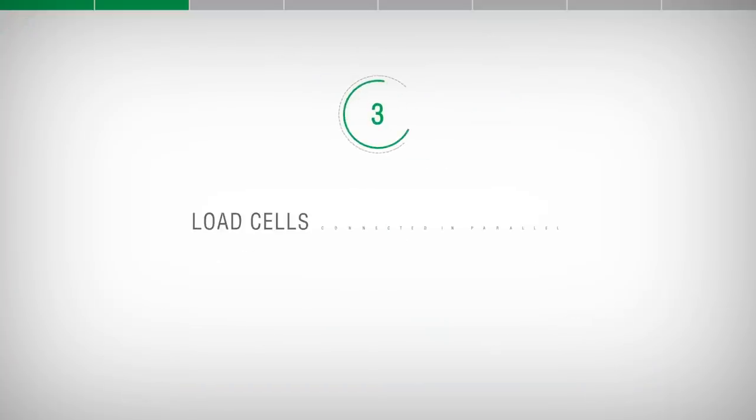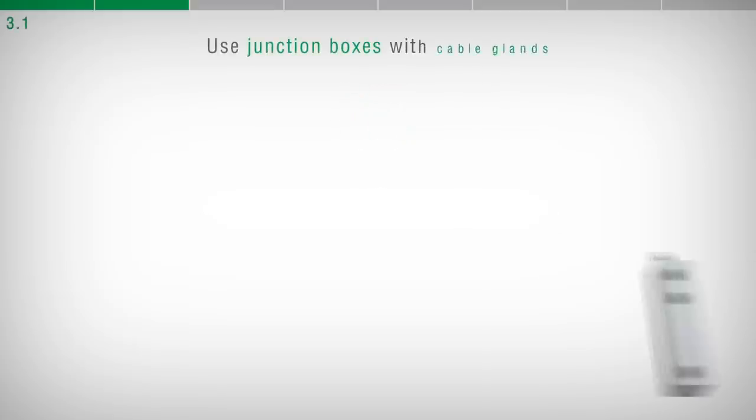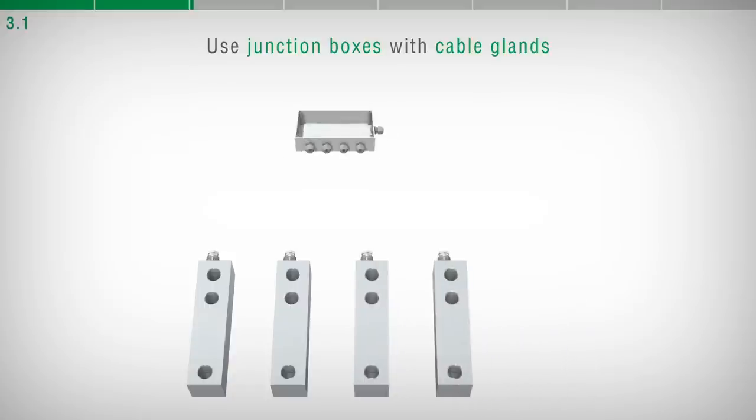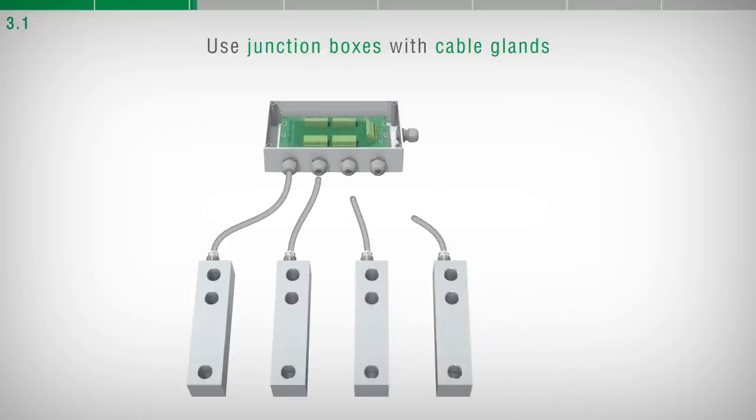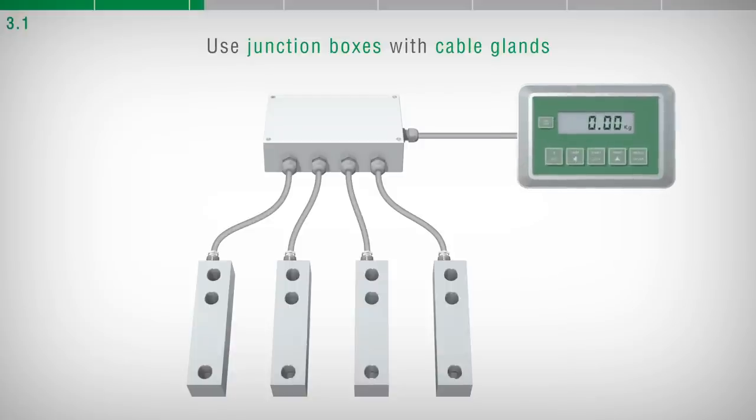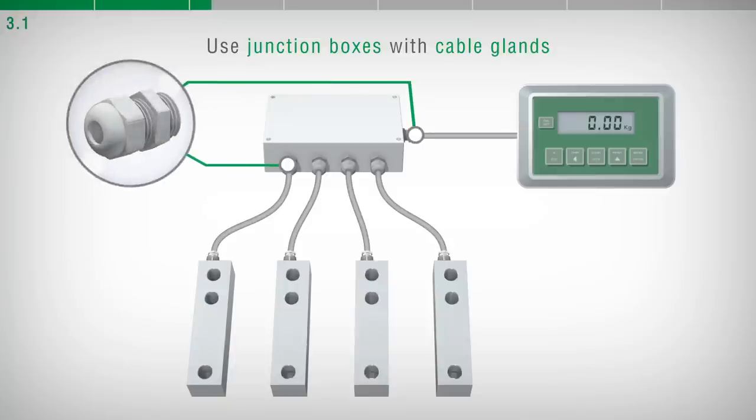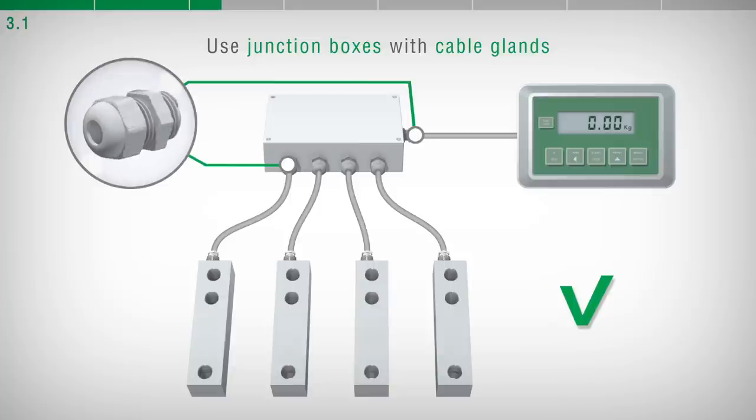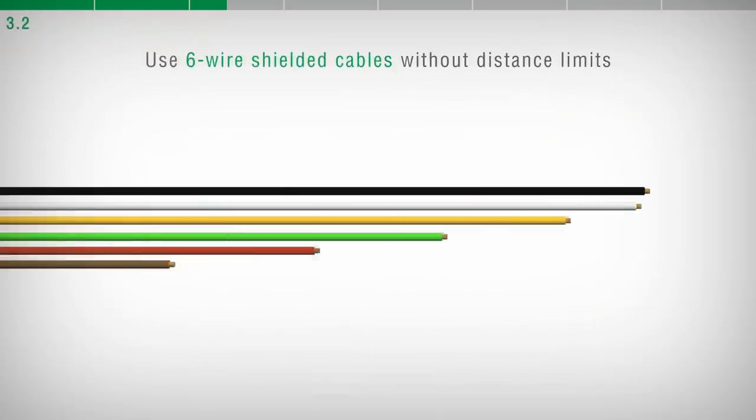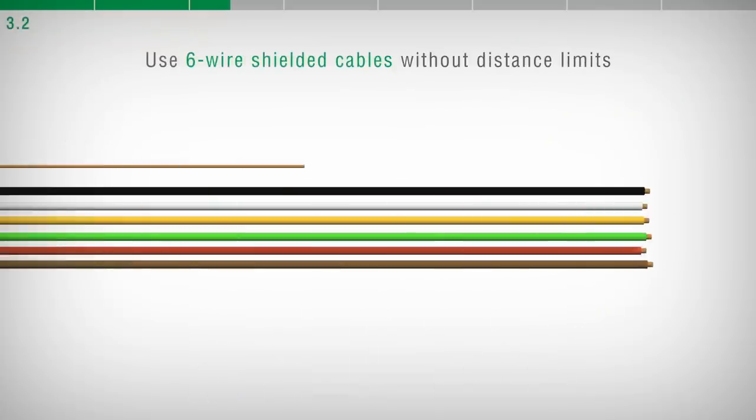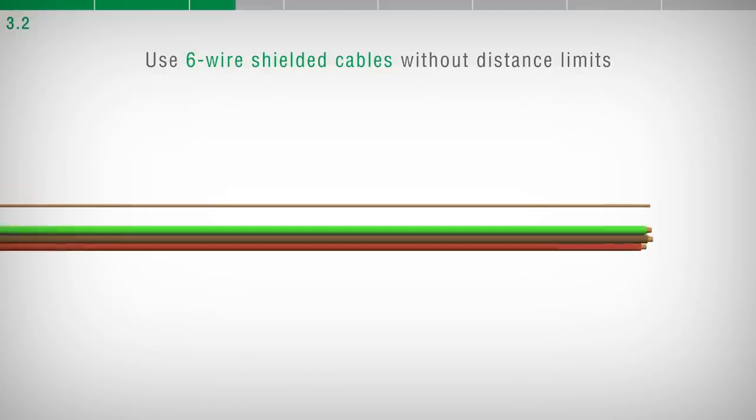Load cells connected in parallel. To connect several load cells in parallel, use a waterproof junction box with a suitable terminal board or a multi-channel transmitter in a box. The incoming and outgoing cables require the installation of cable glands. The extension cables used for connection must be shielded. It is recommended to use a six-wire cable with reference sense management, able to compensate for the voltage drop due to the distance between the devices.